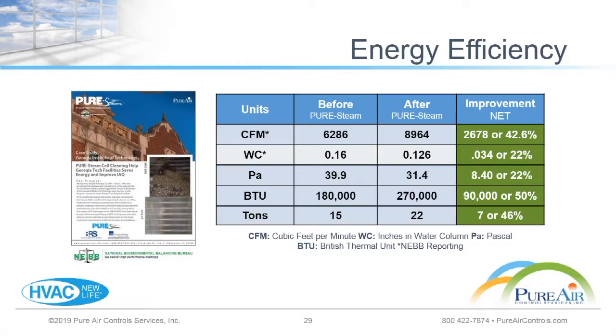Here's another tremendous case study in energy efficiency that we conducted with Georgia Tech University, who also had their own balancing people on site running their own numbers. A NEBB certified report came out of this, and bottom line, we saw a 42.6% improvement in CFM. We really saw some great improvements. In the case of the test air handler, it was operating at about 15 ton capacity, even though it was a 25 ton air handler. At the end of our process, it was actually operating at a 22 ton capacity. So we added essentially 7 tons of air conditioning through this restoration process. Really interesting numbers for a process that doesn't cost that much. When we talk about age of unit, condition of coils, and how it's functioning, we can really get it back to near factory spec with some of these restorations. It's pretty remarkable, the results we've been seeing in the build.